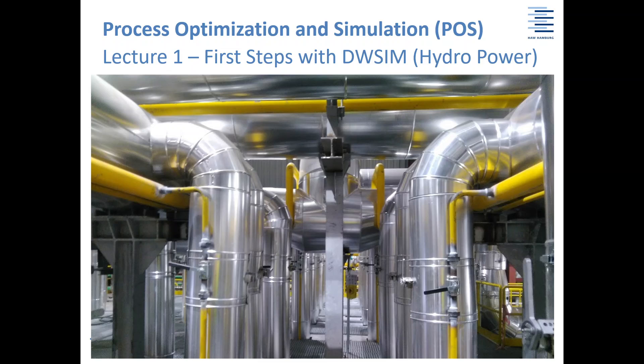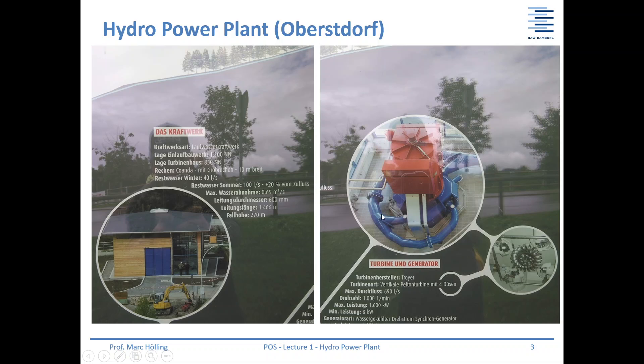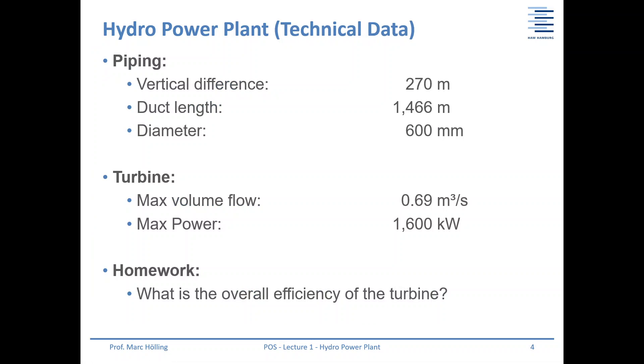This summer I was for one week in Oberstdorf in the Alps, and there I found a quite nice hydropower plant. They gave a lot of information — there was an online screen showing live values of power generated and volume flow through the turbine, and also information boards with a lot of data. Since it's in German, I translated it. The main parameters: elevation of 270 meters, duct length of 1466 meters, diameter of 600 millimeters. For the turbine, maximum volume flow was 0.69 cubic meters per second and maximum power was 1.6 megawatts (1600 kilowatts).